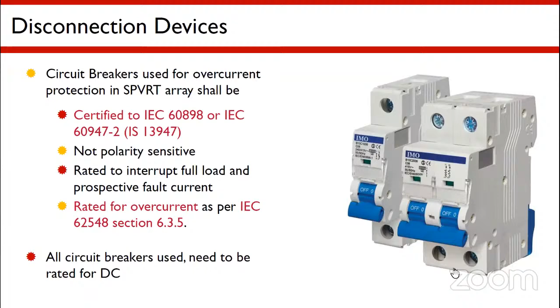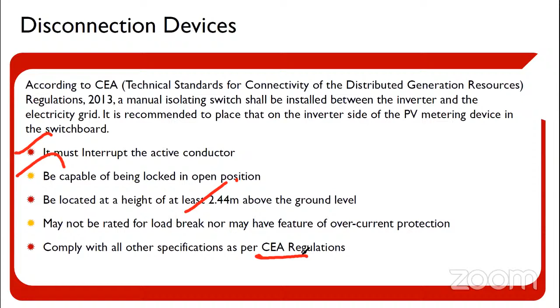And there are very important points with respect to the disconnection device which is being used according to the CEA regulation. First, it must interrupt the active conductor. That is the main condition. Second, it should be capable of being locked in the open position. And third, the height from the ground level is a minimum of 2.44 meters for an isolator or control switch, to provide safety and also to prevent access to the devices by children. Then all the equipment we are using should comply with the CEA regulation. CEA is the Central Electricity Authority.